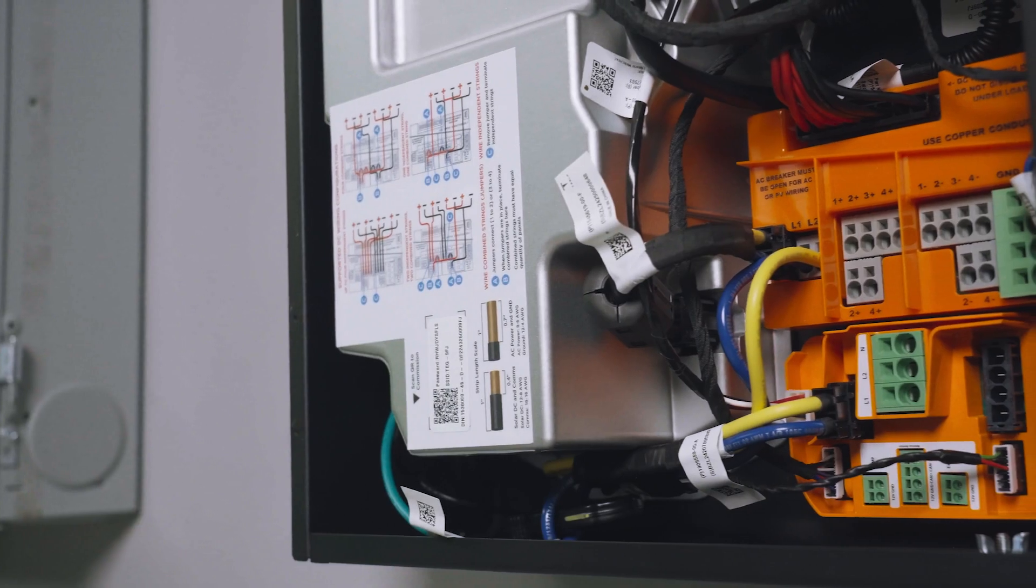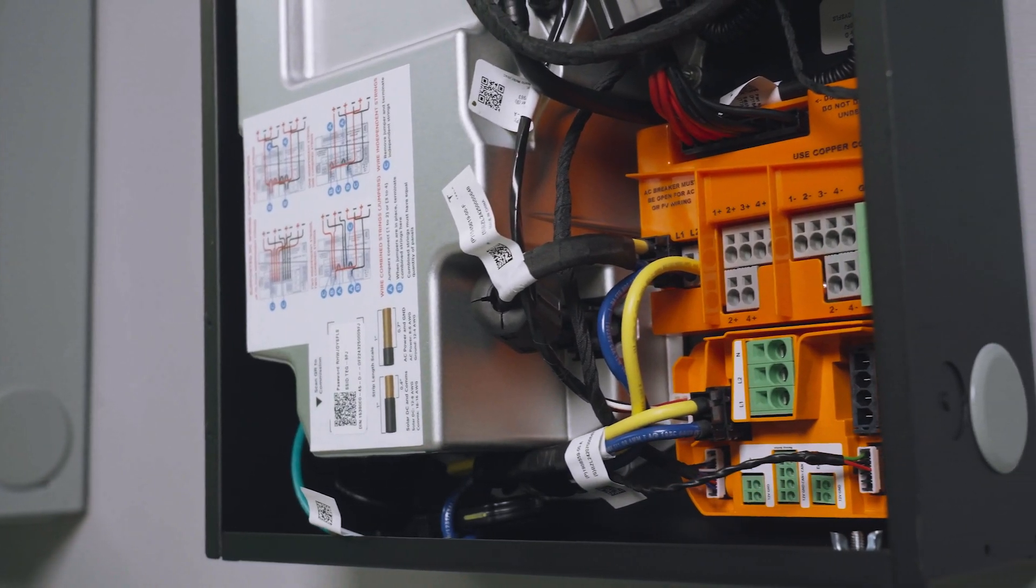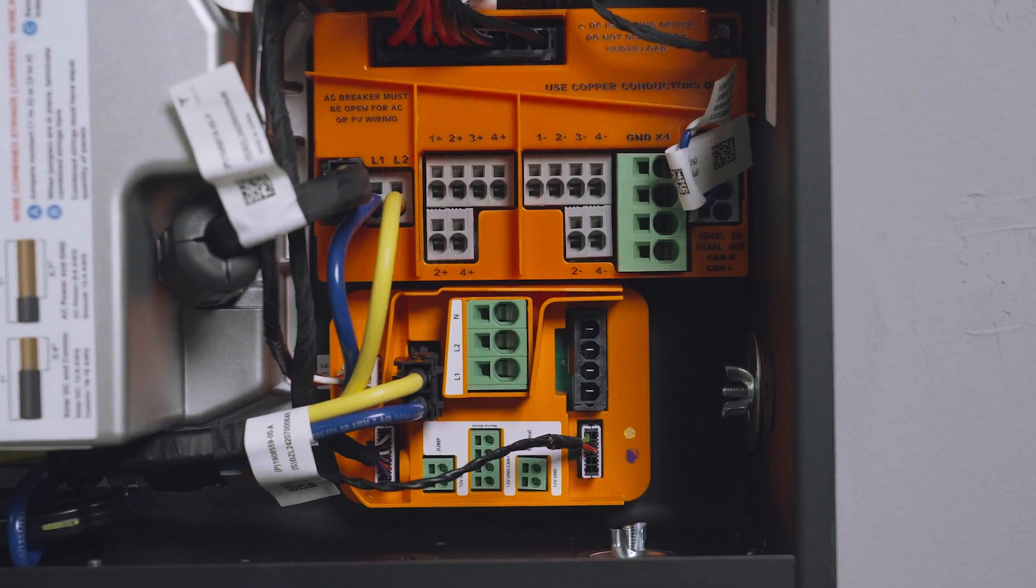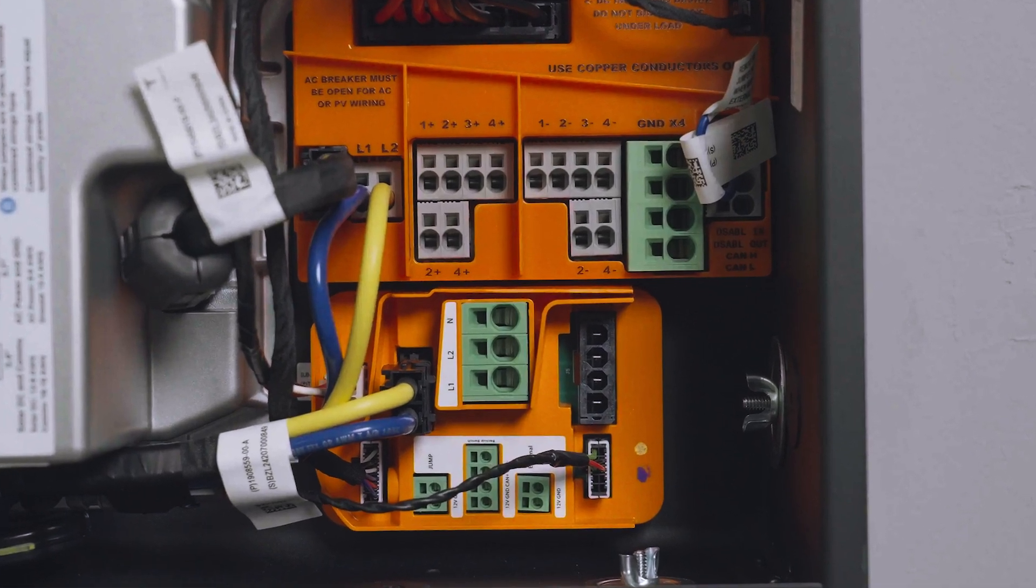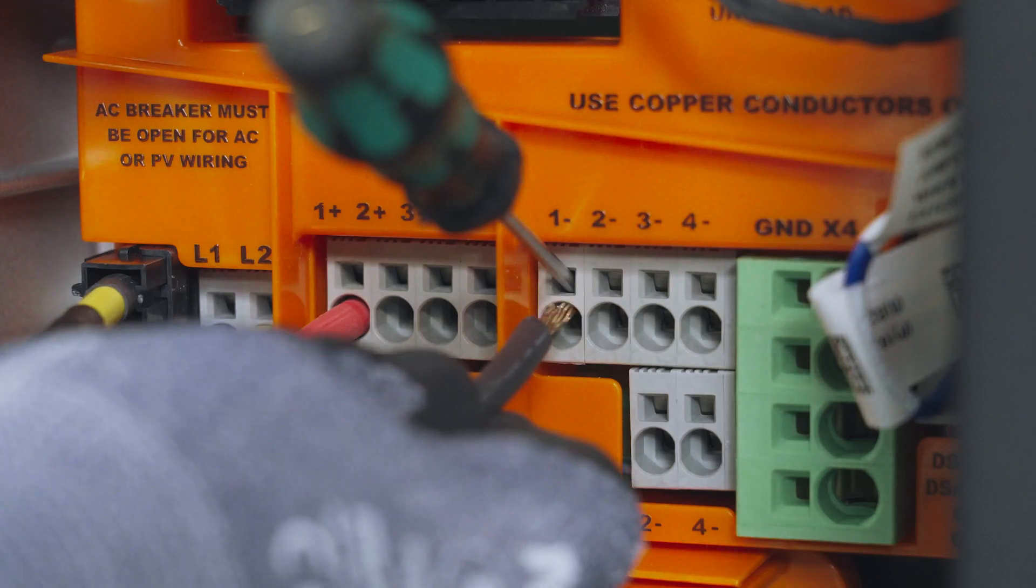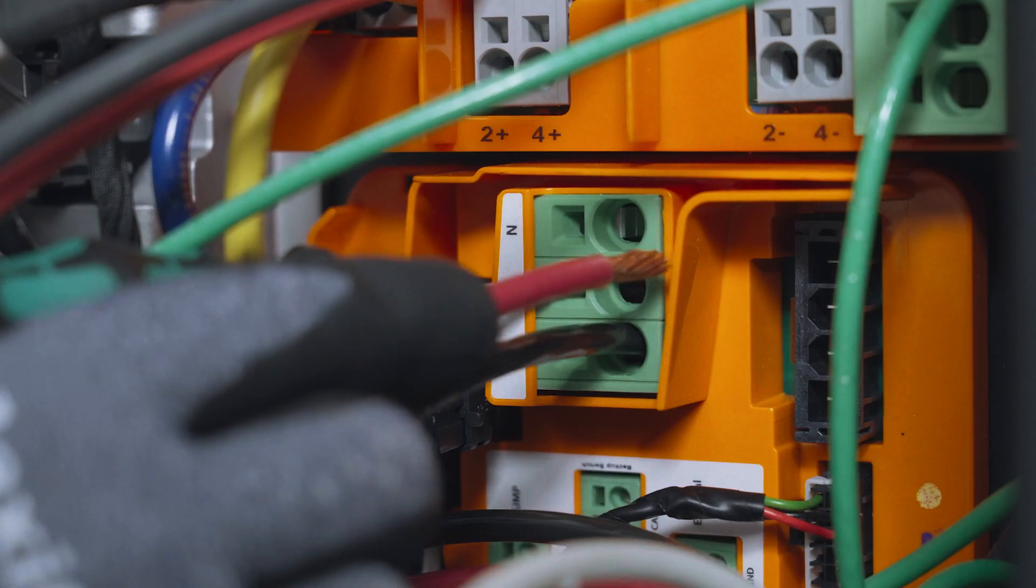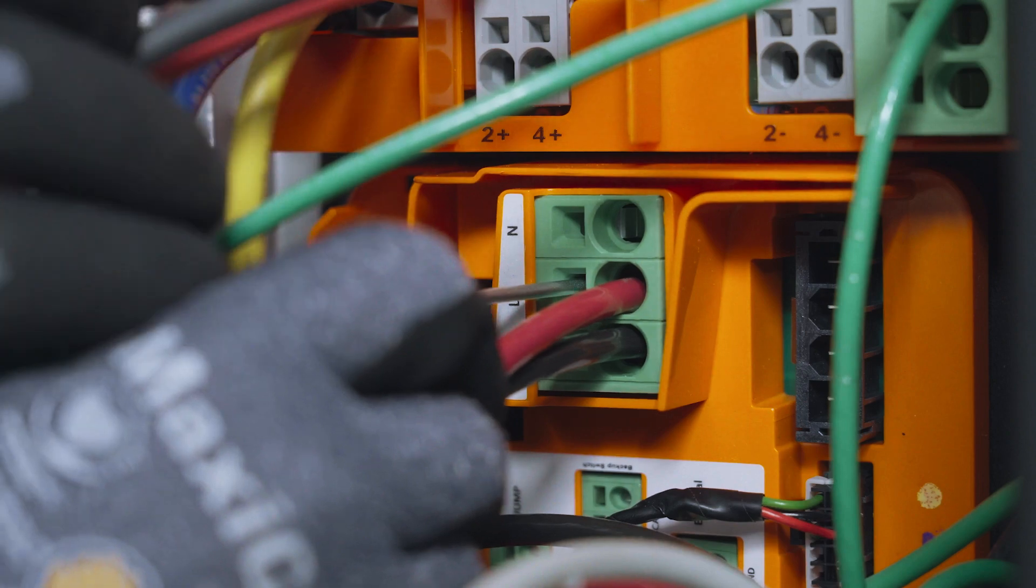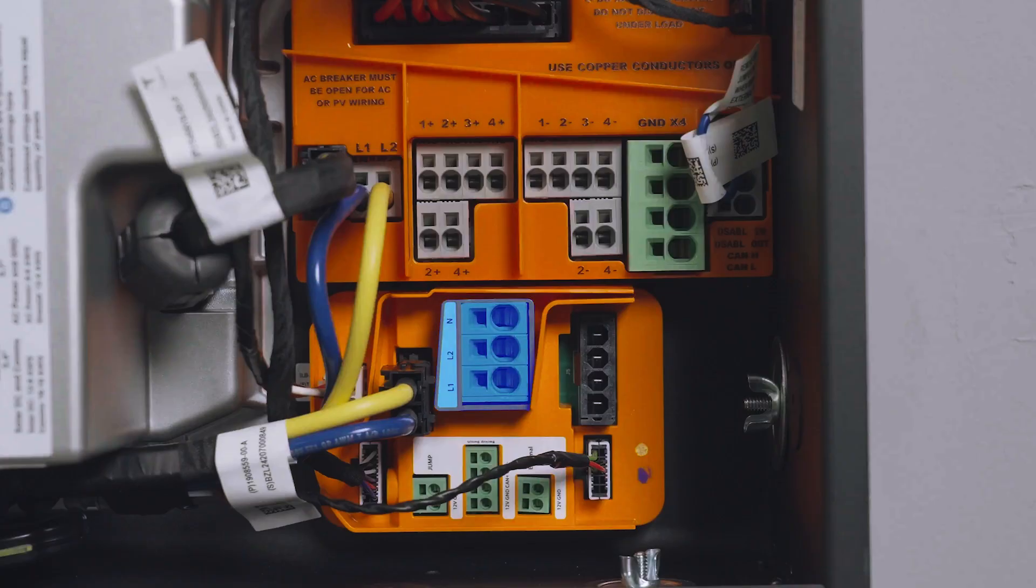Wiring within the inverter can be split into two main types. DC wiring, which connects the inverter to the solar array with positive, negative, and grounding conductors, is terminated here. And AC wiring, which backfeeds the generated power into the home's electrical system, is terminated here.